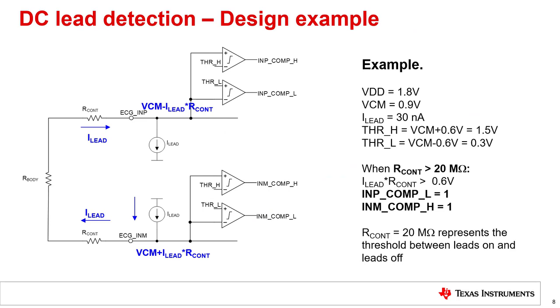Let us look at a design example that illustrates the choices of comparator thresholds and lead detection currents, and the implications of these choices on the threshold of contact impedance between a leads-on and leads-off condition. We take a case where the supply voltage VDD is 1.8 volts. VCM, the target voltage of the input common mode voltage for the RLD loop, is assumed to be VDD/2, which is 0.9 volts. We consider current source-based lead biasing for this design example and assume a lead bias current of 30 nanoamperes. To illustrate both high and low side, we assume a sink lead bias current on the INP side and a source lead bias current on the INM side. The high and low threshold voltages for the comparators are set to 1.5 volts and 0.3 volts, respectively. It is important to choose these threshold voltages outside the normal operating range of the ECG signal chain to avoid a false detection of leads-off condition.